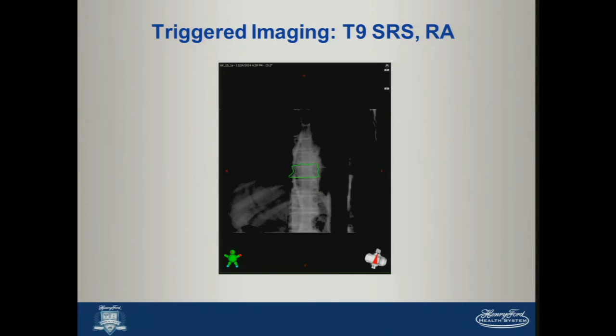So auto beam hold is another feature that's useful to be aware of. So there's going to be a SAMS question on this. Auto beam hold is a triggered imaging application with automatic marker detection and automatic beam hold. It beams on only when the markers are within an allowed radius. And it also allows manual as well as automatic control by operators. So if the therapists want to, they can disable the automatic beam hold and manually beam on when they see the markers go within the target area.